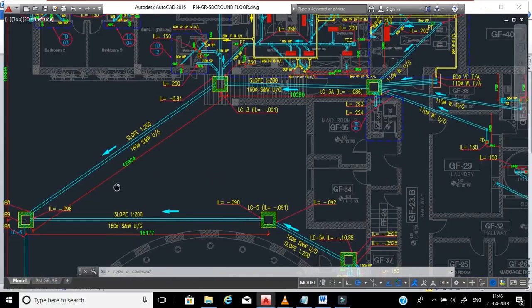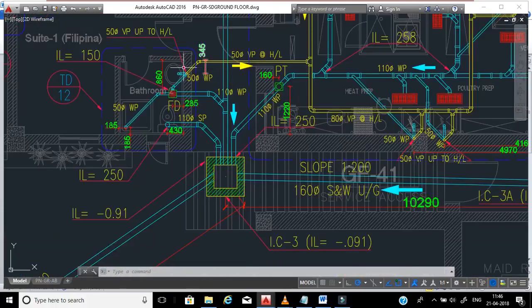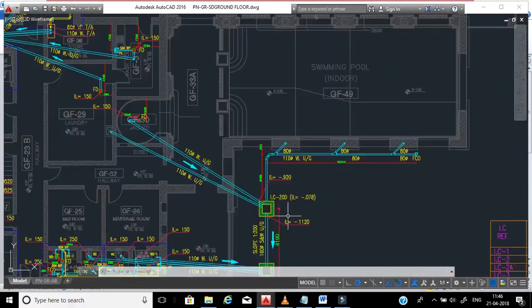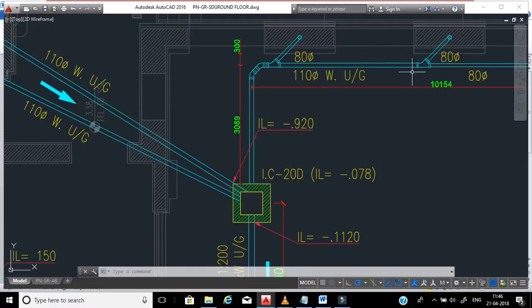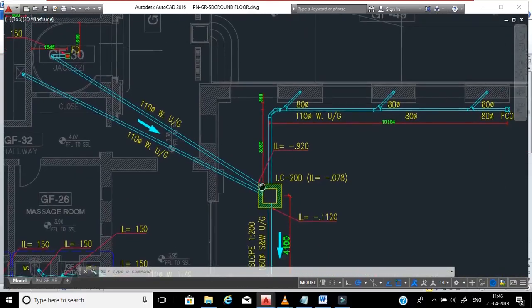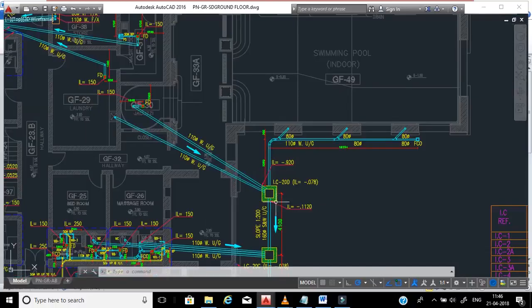When connecting pipes into the manhole, ensure that all incoming pipes are at a higher level than the outgoing pipe. If the incoming drainage comes from here and needs to go out here, it must not be lower - otherwise drainage will return back. You must maintain the slope from the toilet connection point all the way to the manhole to manage it properly.